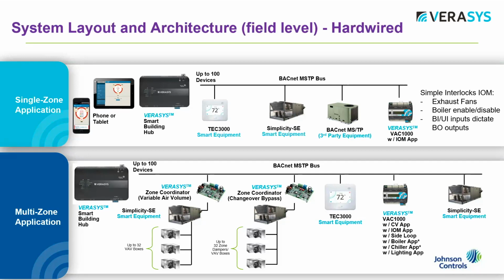We also have this not only for a VAV system, but also changeover bypass. And the nice thing about the way we've set up Verasys is that it's the same zone coordinator, and in some cases, even the same rooftop unit can be used for both of those applications. The only difference is the boxes that we hang below it. Up to 32 zones per zone coordinator, and we're saying maybe up to as many as 5 zone coordinators per hub, and we're listing that with air quotes, because we really have to respect the total point count, which is around 20,000 points in the Verasys hub. I seriously doubt most or almost all light commercial systems will come even close to meeting that requirement.